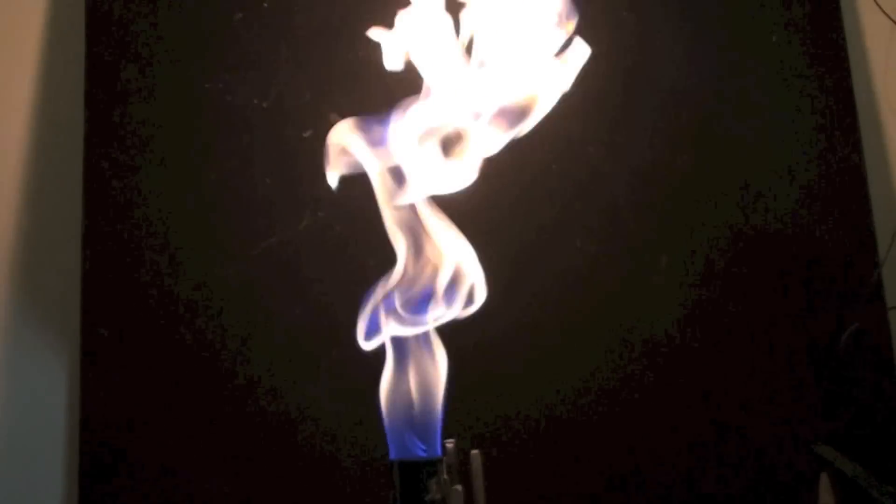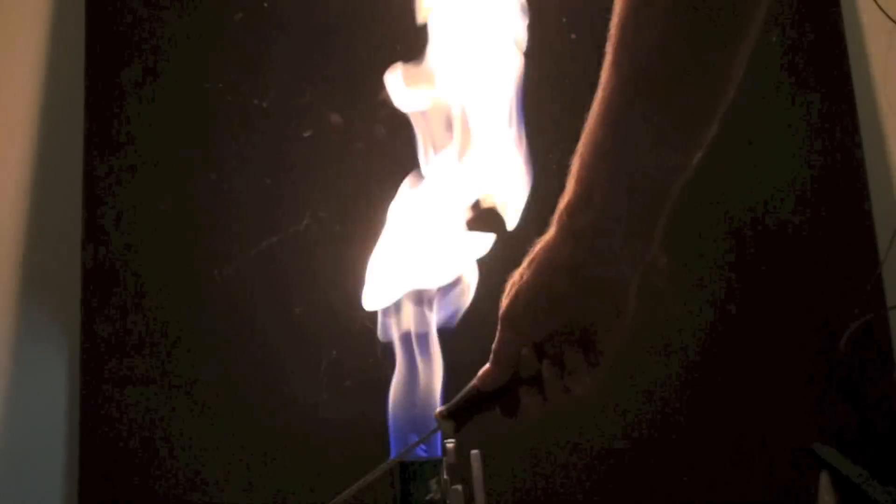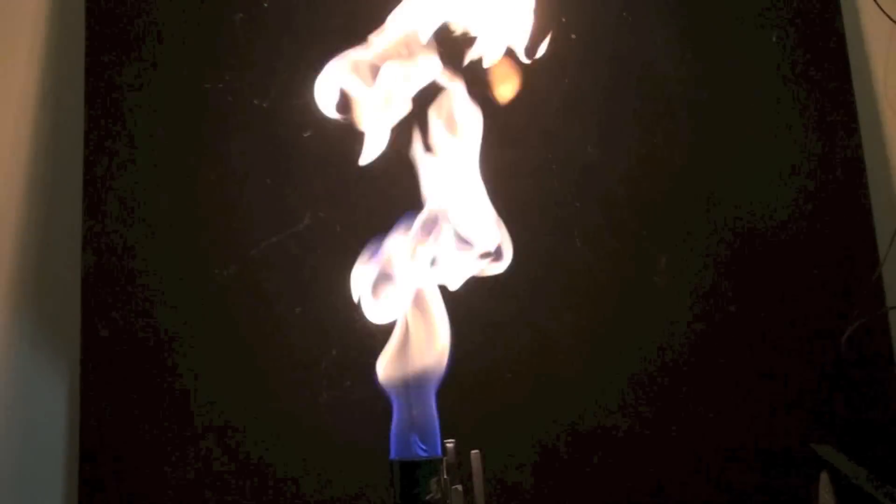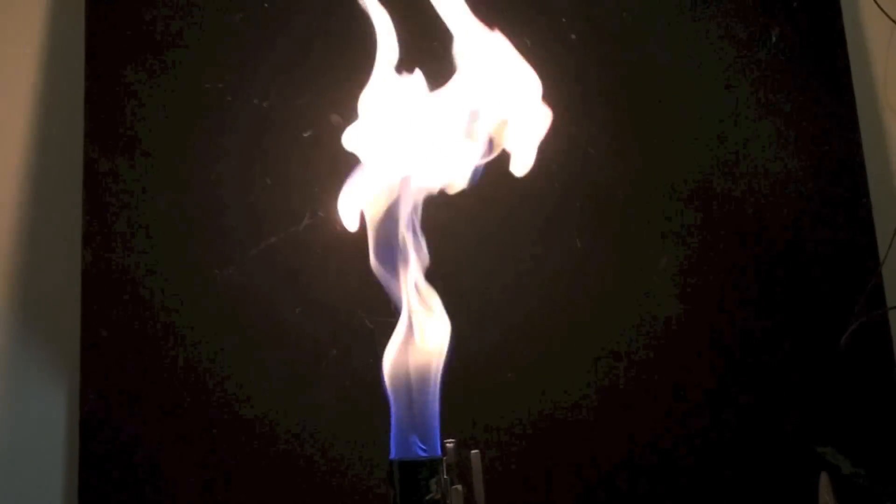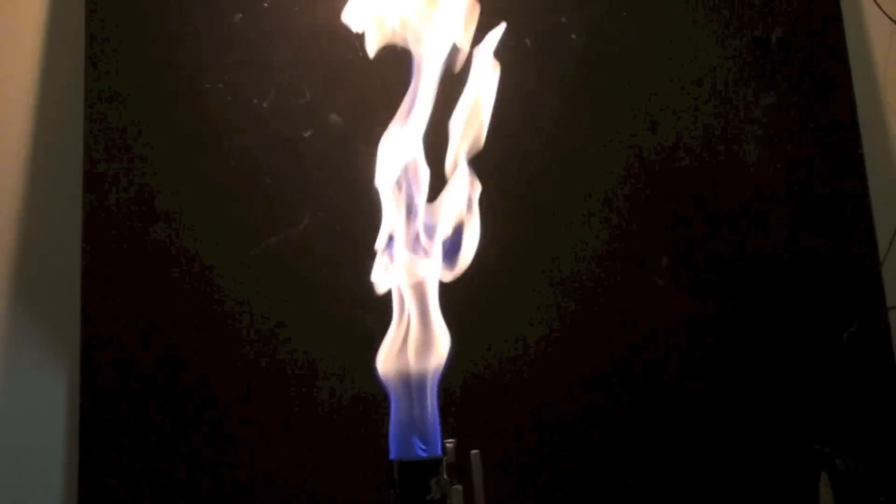This flame, generally, if there's enough secondary air, that's air coming around the sides, does not produce carbon monoxide. However, if it impinges on a heat exchanger or something like that, it will produce carbon monoxide.